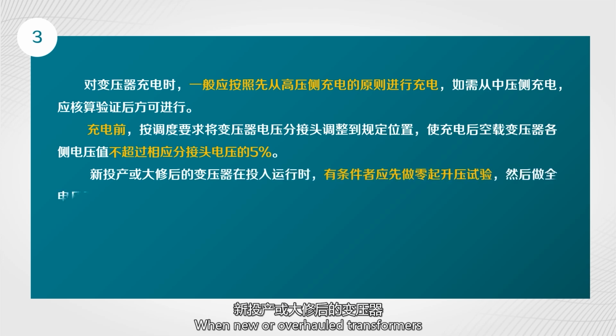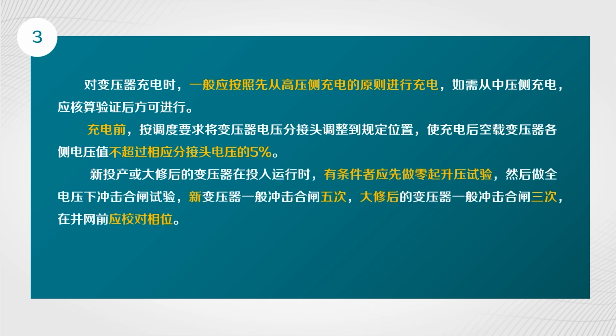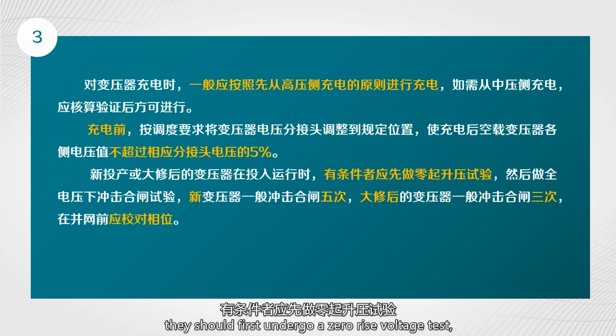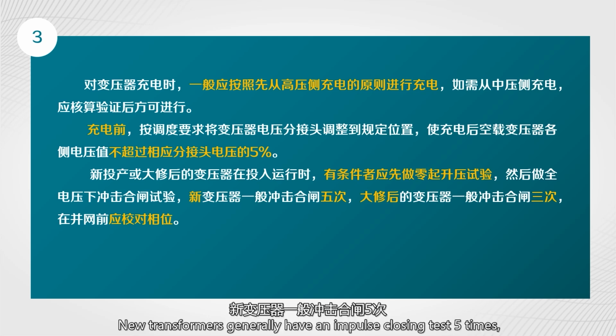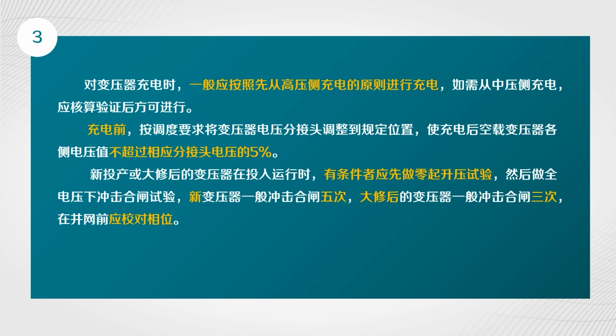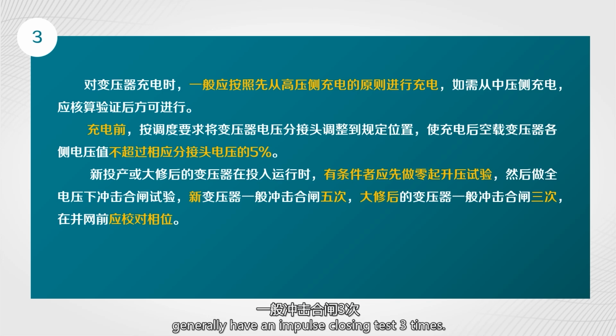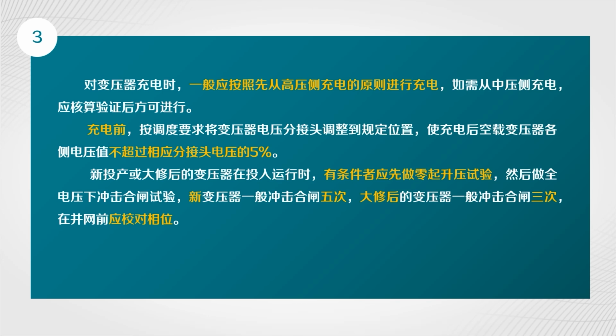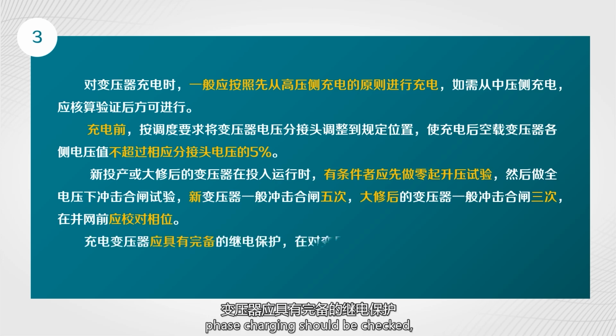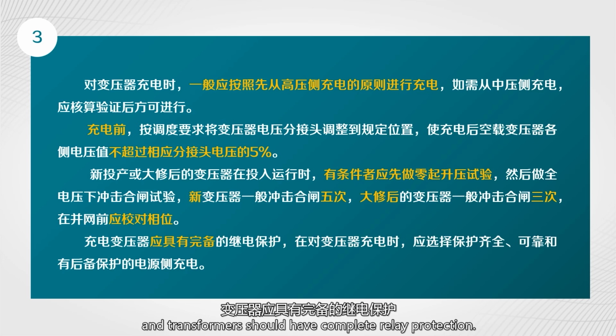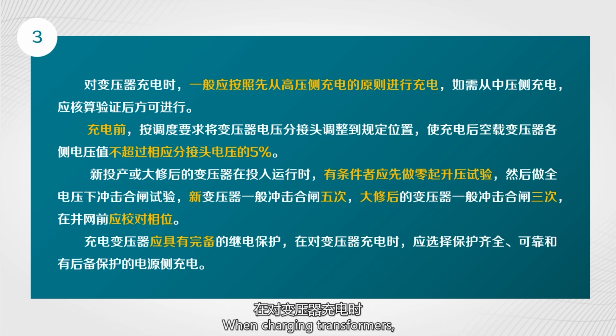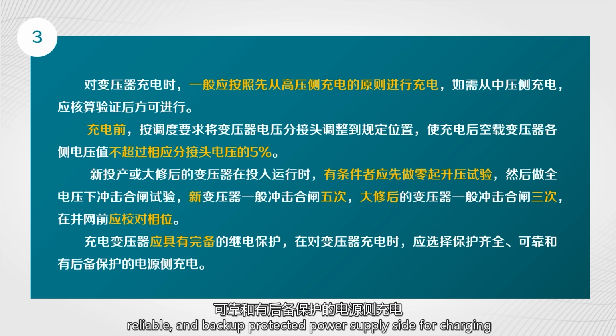When new or overhauled transformers are put into operation, if conditions permit, they should undergo a zero rise voltage test and then undergo an impulse closing test at full voltage. New transformers generally have an impulse closing test 5 times, while the overhauled transformers generally have an impulse closing test 3 times. Before grid connection, phase charging should be checked, and transformers should have complete relay protection. When charging transformers, it is recommended to choose a fully protected, reliable, and backup protected power supply side for charging.